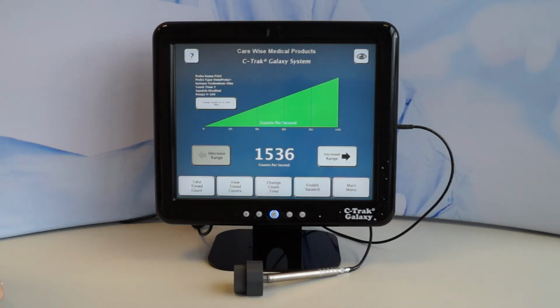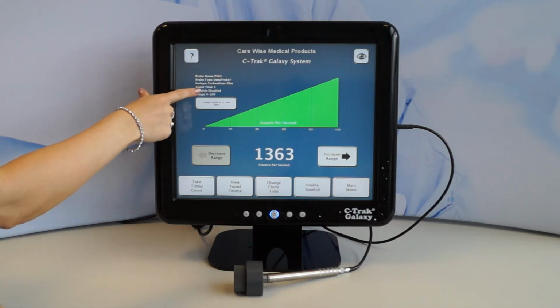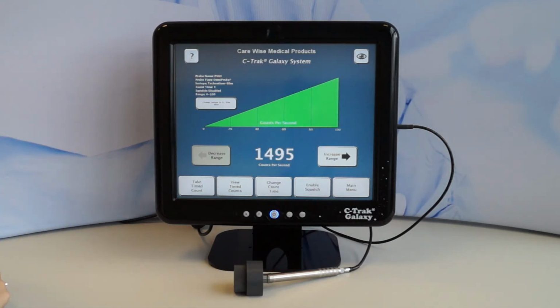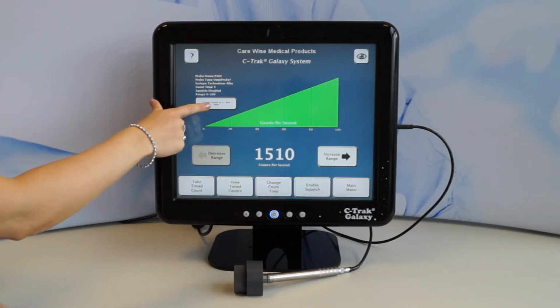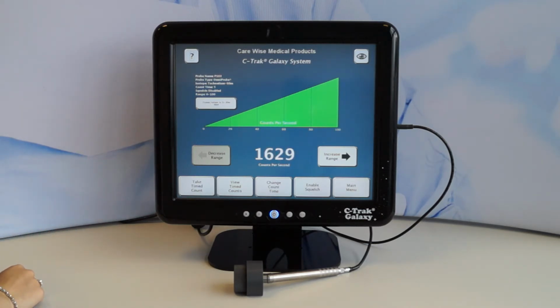The final part on the count screen is the surgical information window. This displays information about which probe is being used and which isotope is being detected. When technetium-99m is selected, a toggle button will appear to switch to technetium-99m wide if radiation uptake is low. This will allow the probe to become more sensitive, but some directionality will be compromised to achieve this greater level of sensitivity. This is useful when radiation uptake is low.